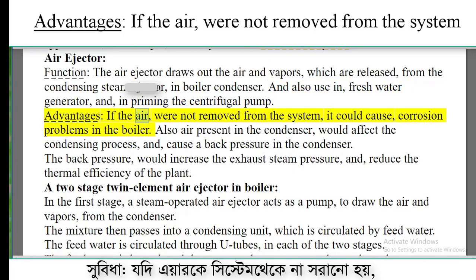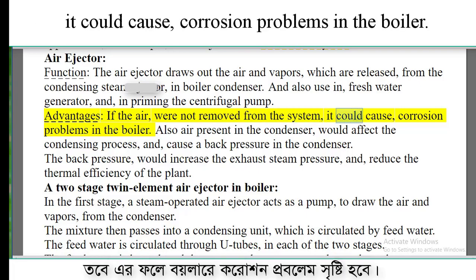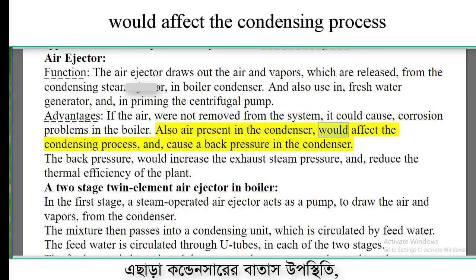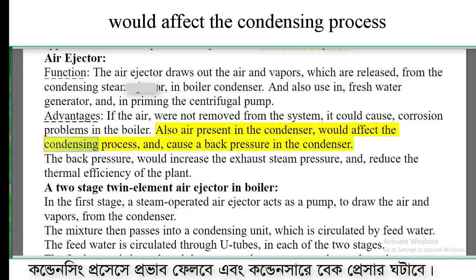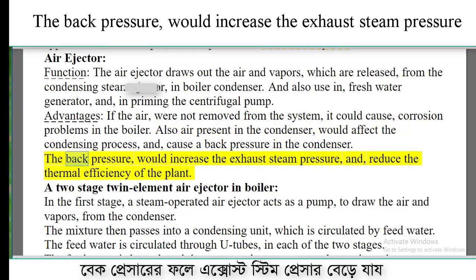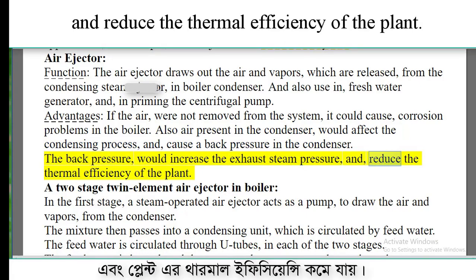Advantages: if the air were not removed from the system, it could cause corrosion problems in the boiler. Also, air present in the condenser would affect the condensing process and cause a back pressure in the condenser. The back pressure would increase the exhaust steam pressure and reduce the thermal efficiency of the plant.